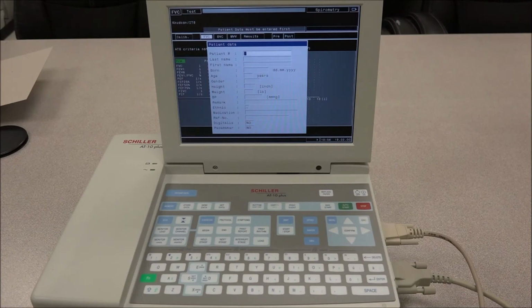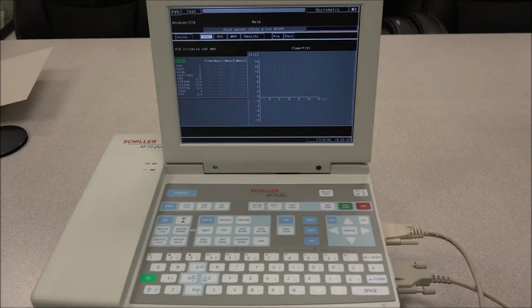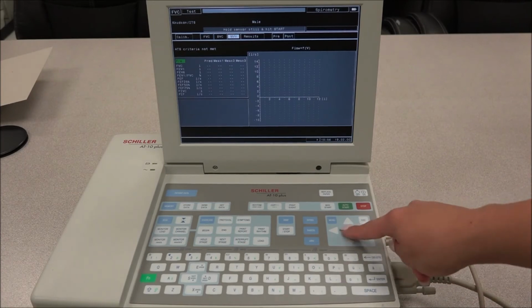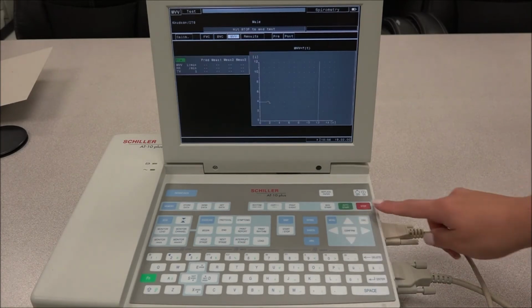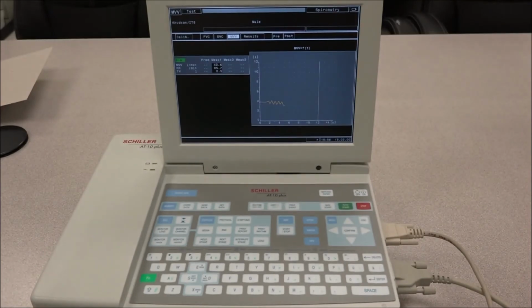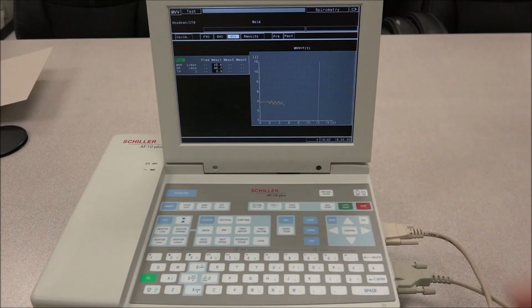Once the unit has been calibrated, set the spiro settings and the norm values through the spiro settings screen. Enter the patient data and select the test that will be performed. All test procedures are carried out in the same manner. Press the start key, and once the test is finished, press the stop key. Once the stop key is pressed, the curve of the last test taken is shown on the screen along with the measurement results. It is recommended that a minimum of 3 measurements are taken.